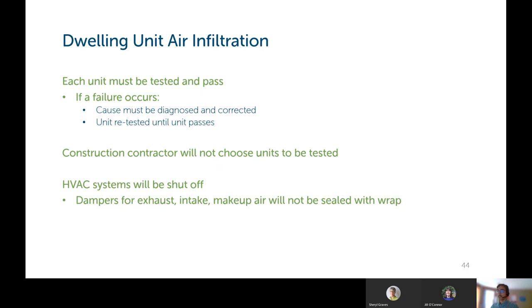The construction contractor will not be the one who chooses the units to be tested. That will be more on a random basis, meeting the requirements for number of units per floor. And the HVAC systems will be shut off during the test, but dampers for exhaust, air intake, and makeup air units will not be sealed up with plastic wrap.